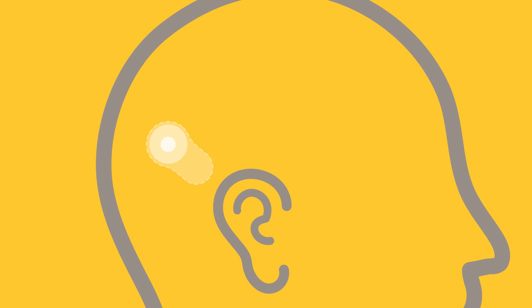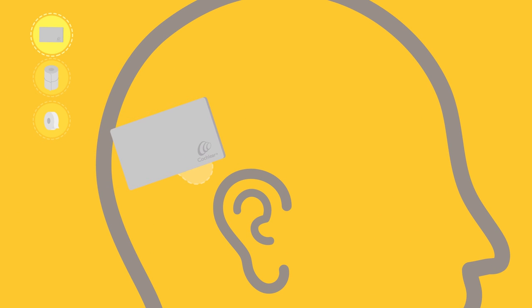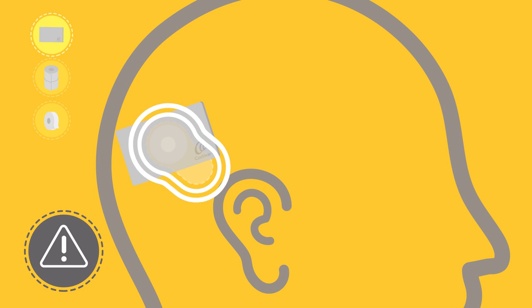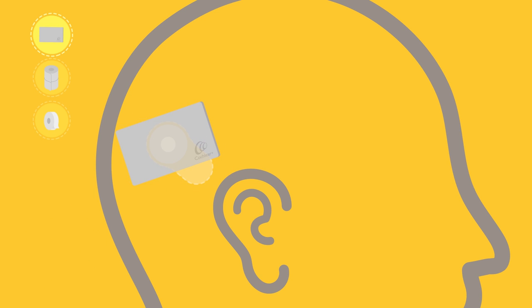Once the implant magnet has been successfully located, centre the splint from the MRI kit over the implant magnet site and press against the skin. The splint should put pressure over the implant magnet, not the implant body. Ensure that the splint is held in place and then use the supplied surgical tape to keep it in position.